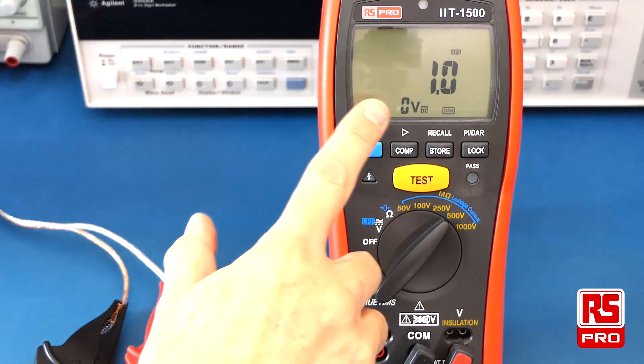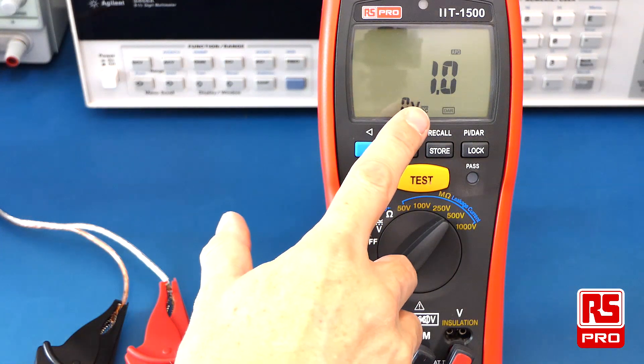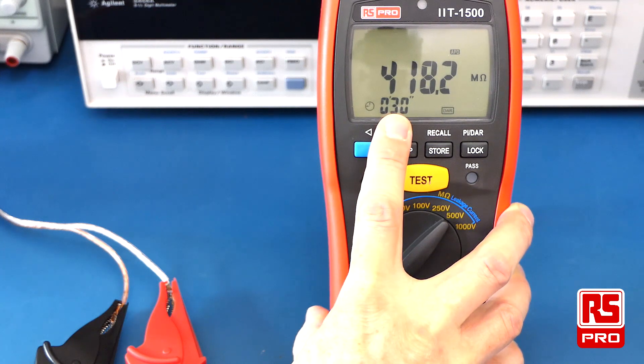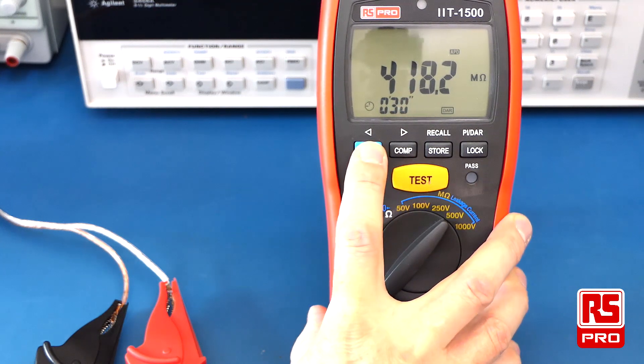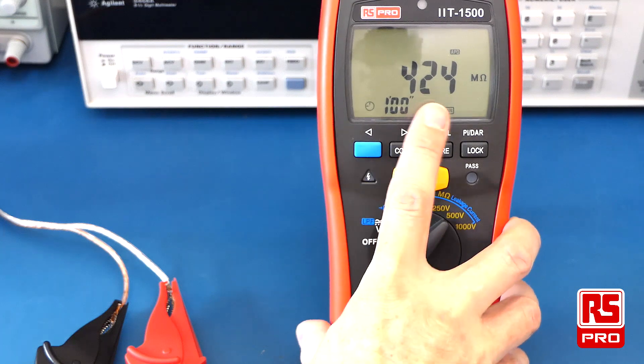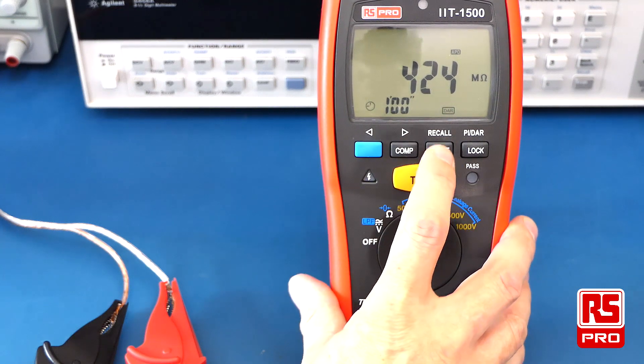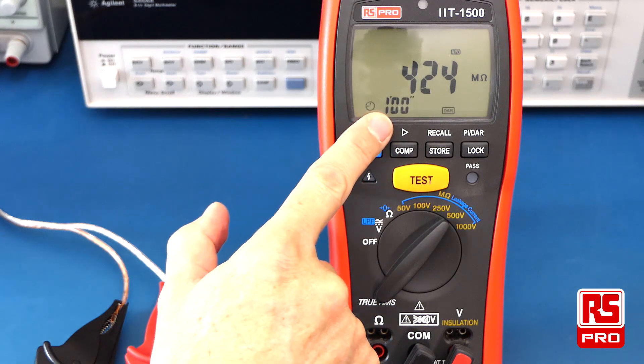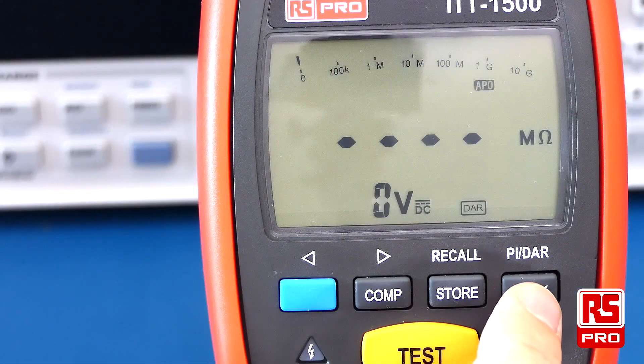Once the test completes, the result will be displayed on the screen. Pushing the blue function button will show you the reading at 30 seconds and then the reading at 1 minute. To save these results, simply push the store button — here it's stored in memory location 1. To exit any PI or DAR test, simply hold down the PI/DAR button and the icon will disappear.